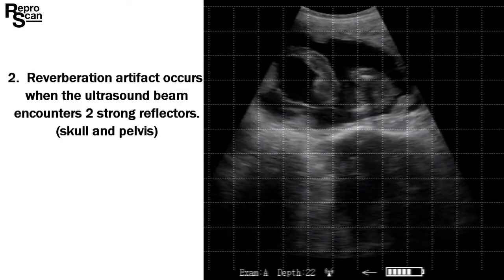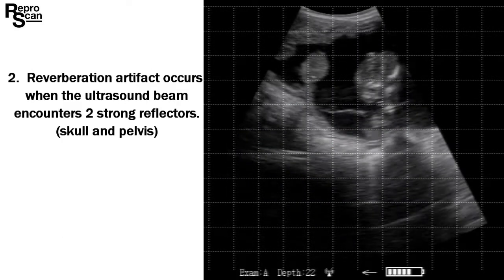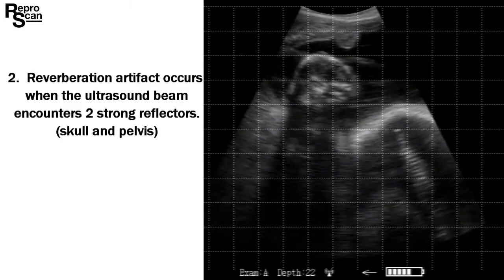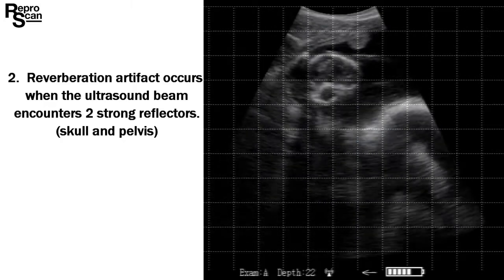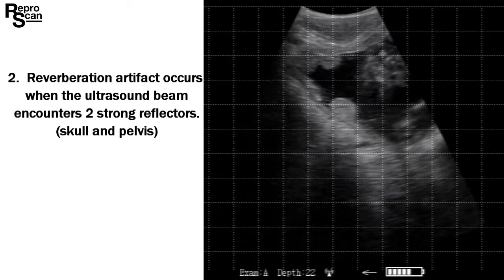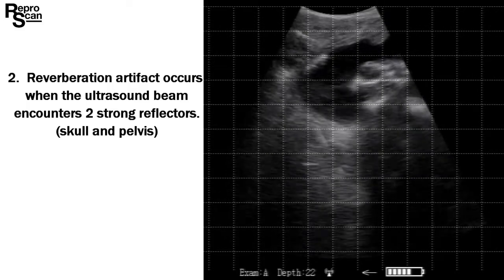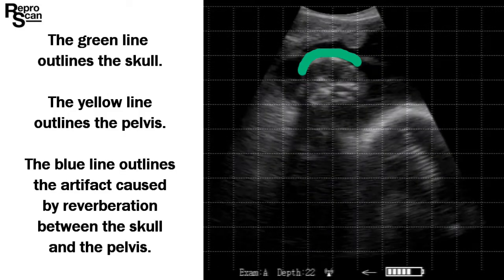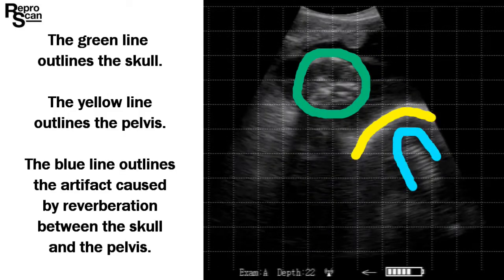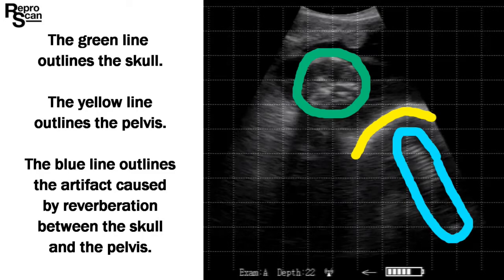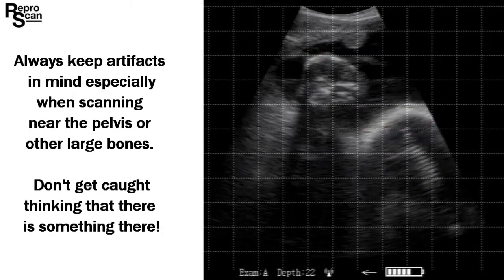A second reverberation artifact occurs when the ultrasound beam encounters two strong reflectors — in this case the skull and the pelvis. The green line outlines the skull, the yellow line outlines the pelvis, and the blue line outlines the artifact caused by the reverberation between the skull and the pelvis.